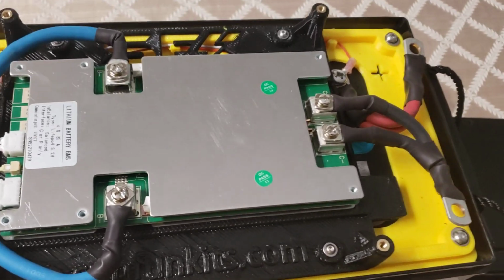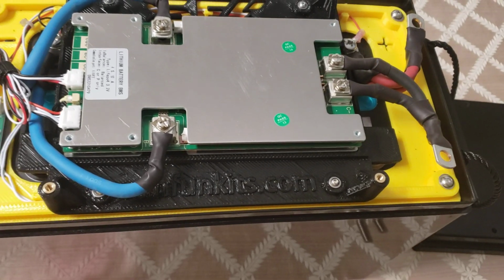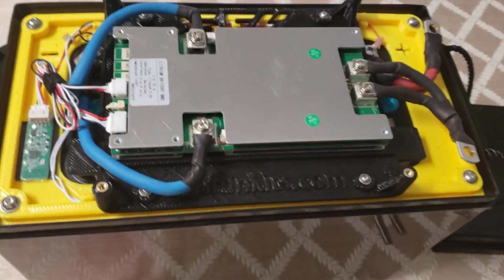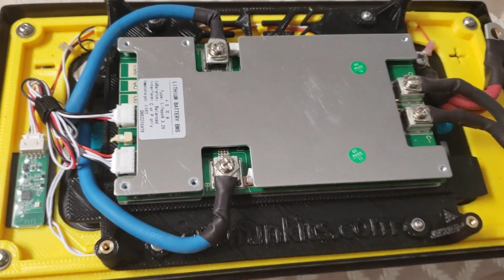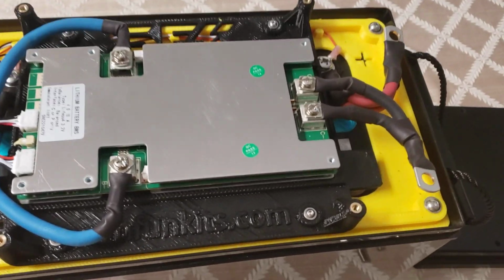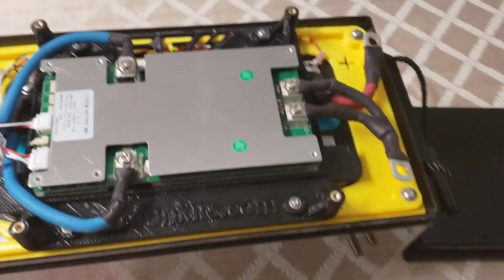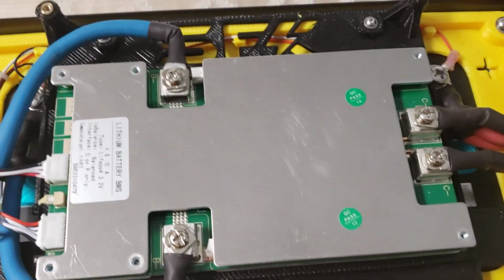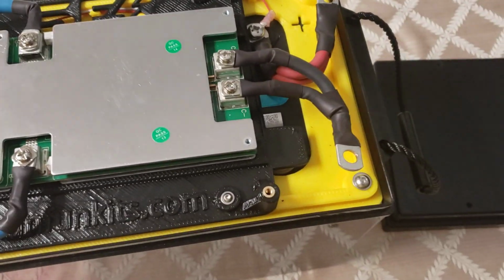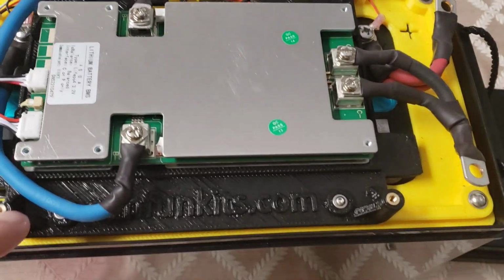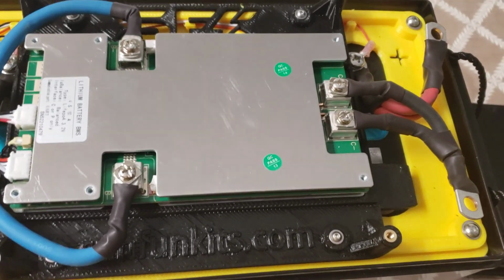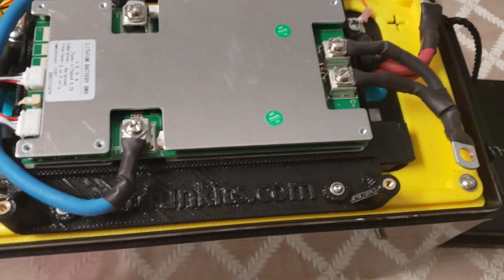However, I recommend, and the way it comes from the factory, it will be set at 100 amp continuous discharge. Should you want, if you get the kit option, you can change it for up to 150 amps. Now we're going to take off the top plate to show you how the bus bars and other things are set up.